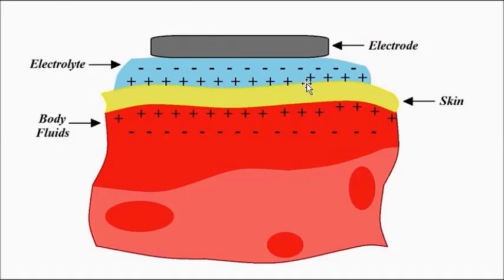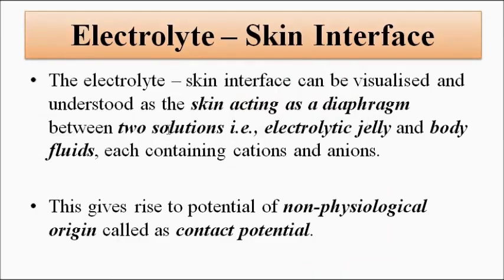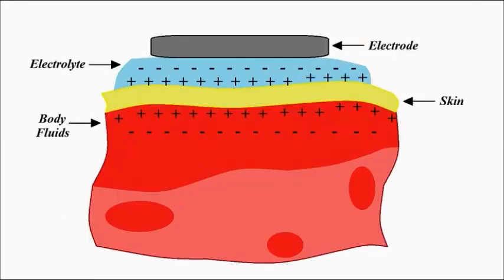We can visualize the skin as a diaphragm between the two solutions — the electrolytic jelly or electrode paste and the body fluids. Because of this arrangement, an electric potential of non-physiological nature is generated along with the biopotential, along with the physiological signal of interest. This extra non-physiological potential is mostly called the contact potential.